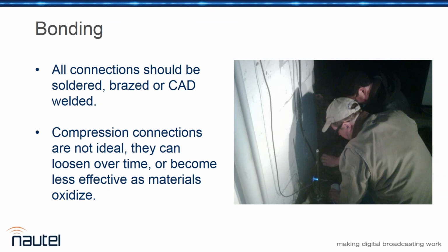Mike, do you have input on that? I try to avoid clamped connections whenever possible. My experience has been like yours—the copper settles or compresses, maybe it's a thermal cycling issue, I don't know, but you come back six months or a year or two later and it's loose or looser than it should be. So the only time I ever sign off on a clamped connection is when there's a good reason not to weld it, like if welding it on the leg of the tower would cause it to collapse. Otherwise, always proactively braze, solder, or CAD weld—some sort of metal-to-metal connection where the metal actually flows.